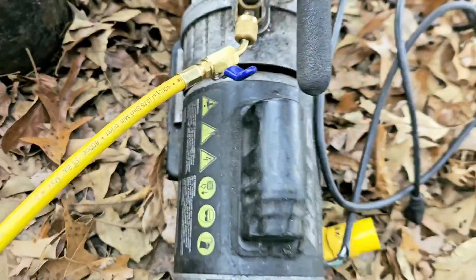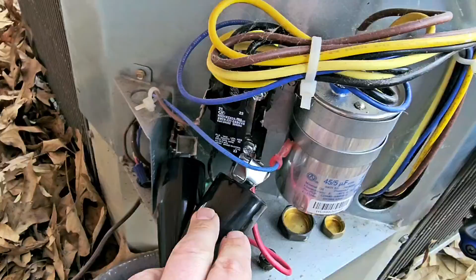Connecting the pump. Go ahead and plug in the little cord, the little adapter cord. We're taking the power from the contactor, and I've got one of the coil wires off the contactor so it doesn't energize the compressor. So I should be able to just flip that on, flip that on. Pull that vacuum, and then we'll open these valves back up, test the cooling, test the heating, make sure everything works. Vacuum pump is done.